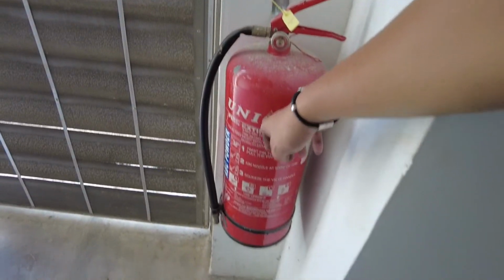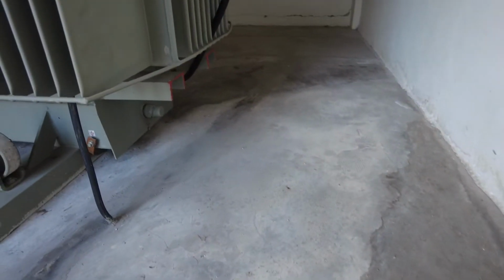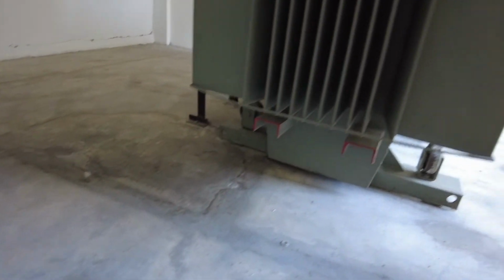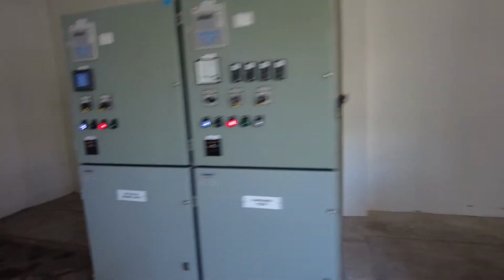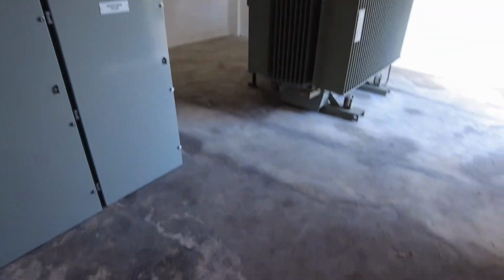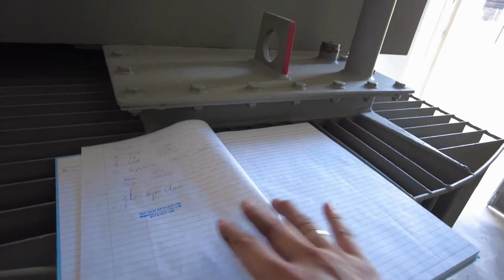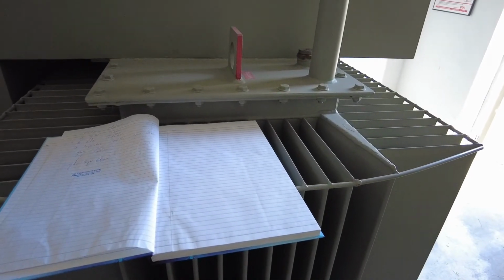Okay, here, this is an ABC fire extinguisher. I have to change to CO2. There's no oil leakage. Everything okay, no oil leakage. This is an AM SGB transformer. It's 1000 kVA. Overall of the room. Alright, then write into the logbook. Okay, we have checked everything. Now okay. Bye bye.